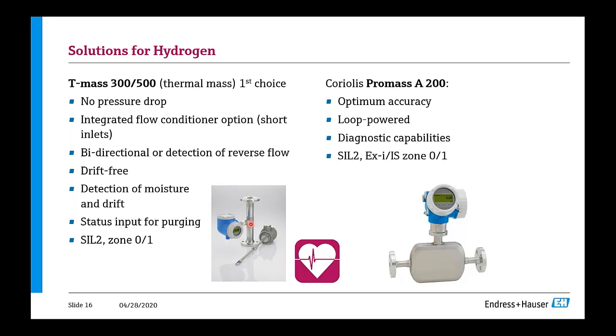These meters are drift-free, the new sensors that we've got, and they can detect moisture and drift using Heartbeat Technology. We also come with a status input for purging. If you switch between hydrogen and air for air purging, you can actually measure both using this meter. This is beautiful for this technology. And it comes with SIL2. This is, however, still pending approval, which takes some months, maybe.